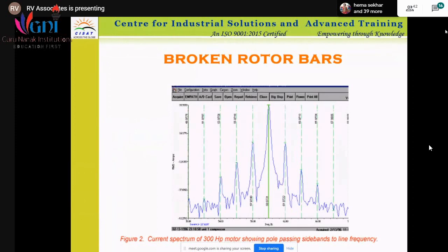This is one of the case studies where there are broken rotor bars. It may be the rotor rings. If the rotor rings fail, a rotor bar will fail. See the pattern. There is no same pattern; at one place you can see the change. That particular bar has been analyzed, and it shows which particular bar has failed. So it gives you the result as well as the analysis. This is what broken rotor bars look like.